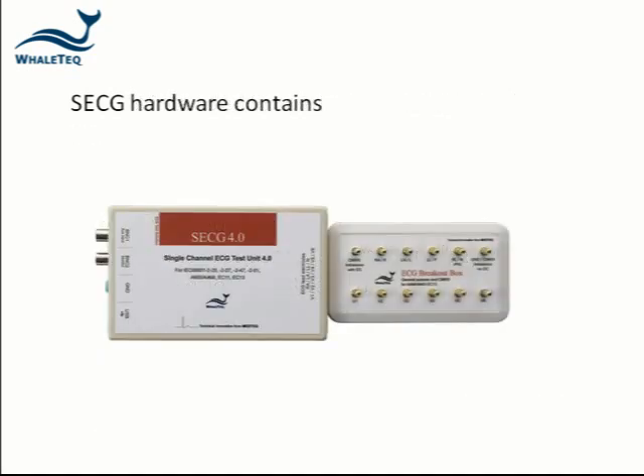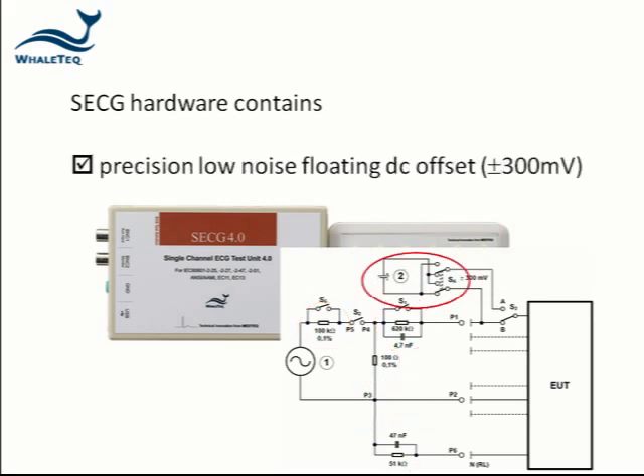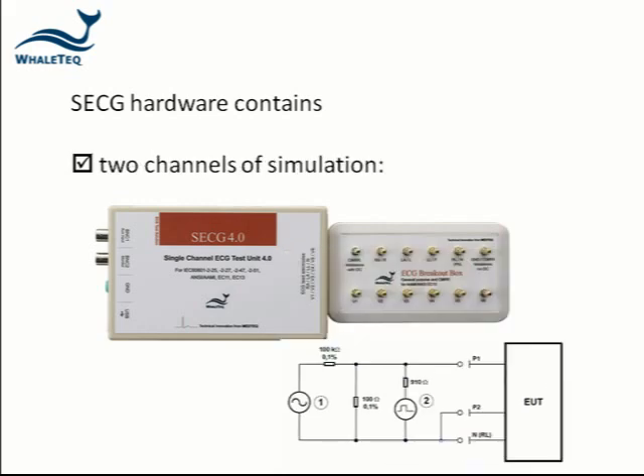The hardware box contains resistor-capacitor networks as required by the standard, a precision low noise floating DC offset of plus or minus 300 millivolts, relay switching including allowing the user to select the output electrode, and two channels of voltage simulation.